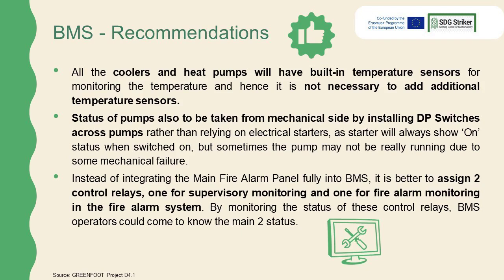Instead of integrating the main fire alarm panel fully into BMS, it is better to assign two control relays, one for supervisory monitoring and one for fire alarm monitoring in the fire alarm system. By monitoring the status of these control relays, BMS operators could come to know the main two status.